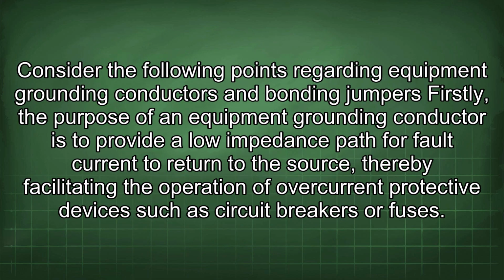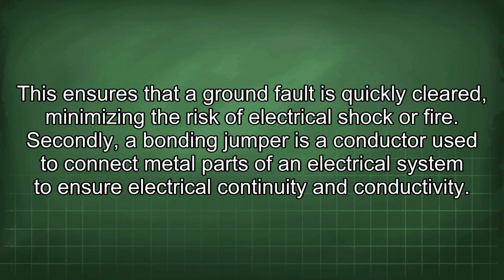Consider the following points regarding equipment grounding conductors and bonding jumpers. Firstly, the purpose of an equipment grounding conductor is to provide a low impedance path for fault current to return to the source, thereby facilitating the operation of overcurrent protective devices such as circuit breakers or fuses. This ensures that a ground fault is quickly cleared, minimizing the risk of electrical shock or fire.